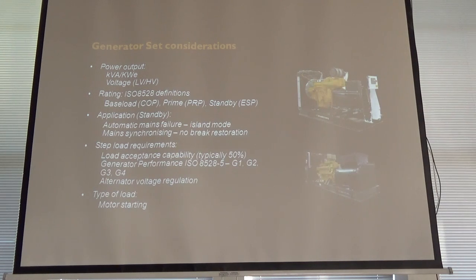Now if it's a hospital, say an 11 kV ring, a hospital, say Peterborough Hospital has 6 MVA of generators there. It's an N+1 basis, in other words a spare set, so the actual maximum power requirement they deem they'll need is 4 MVA of power. Now the rating differences are key. For instance, if you have a substation that goes down, that hospital wants those sets to run at a variable profile for an unlimited period of time. In other words, it's not limited.